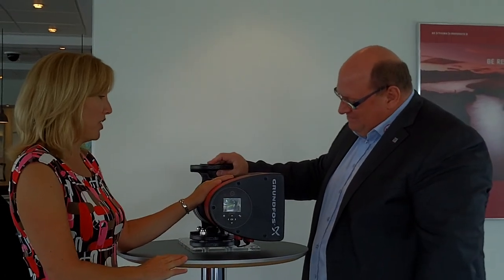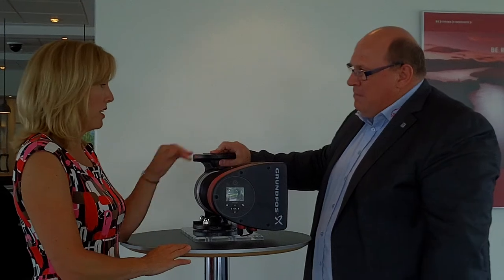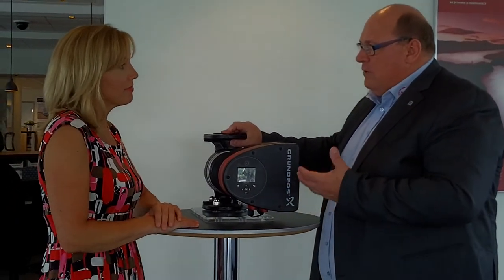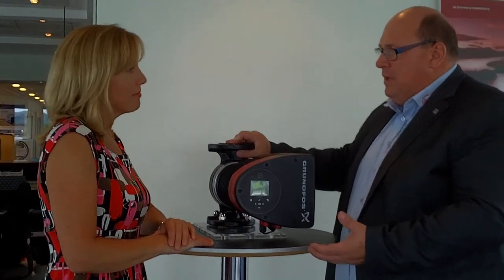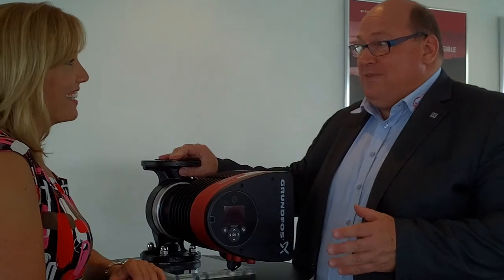This particular circulator pump is used mainly in HVAC applications. But we can also use it for ground source heating now, because we can go down in temperature to minus 10 degrees Celsius — which is around 14 degrees Fahrenheit.